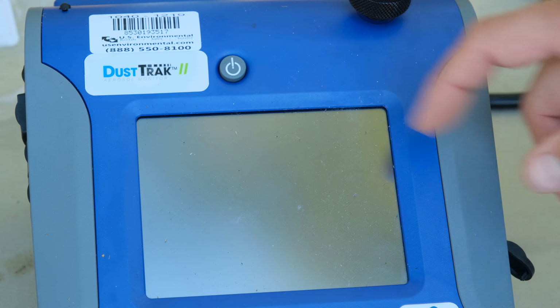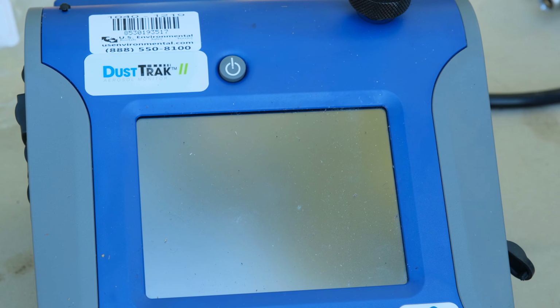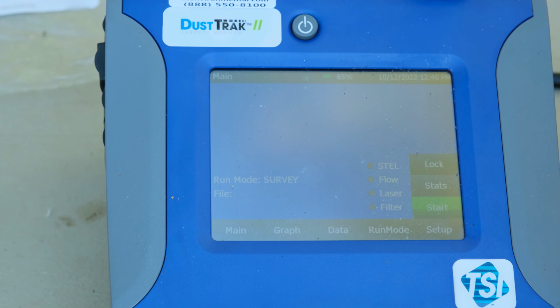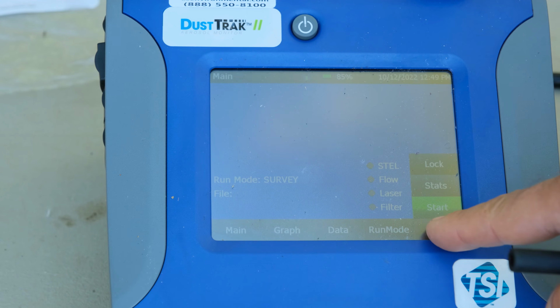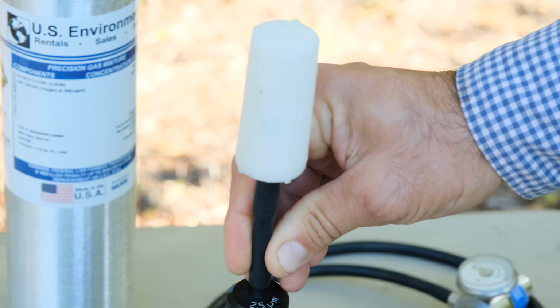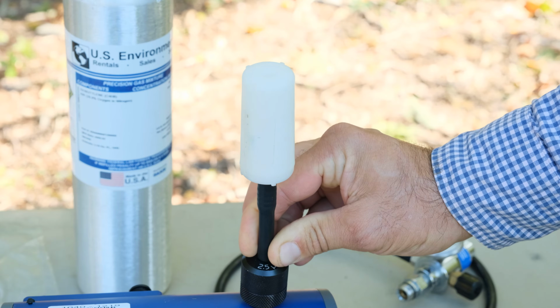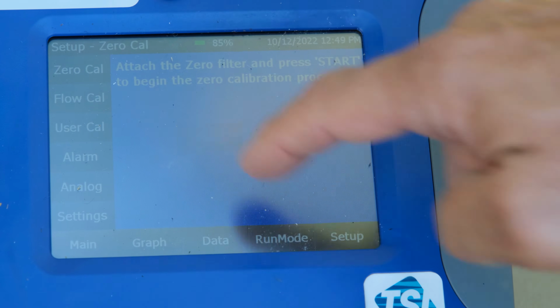So from startup on calibration, you're gonna hit that power button. You'll see the TSI logo when you boot it up. All right, you'll see this main dashboard come up. Next, you'll head over to setup down at the bottom right corner there. You want to install your calibration filter up there at the top. Go ahead and press 0 cal and start her up.